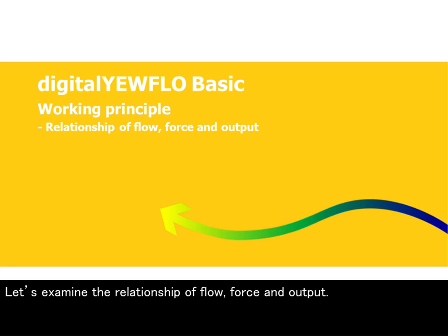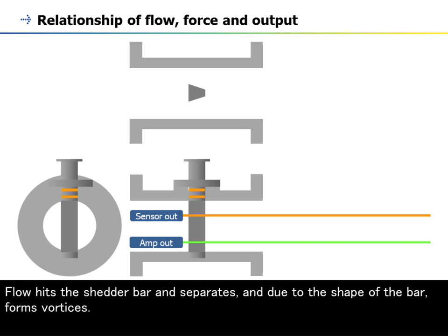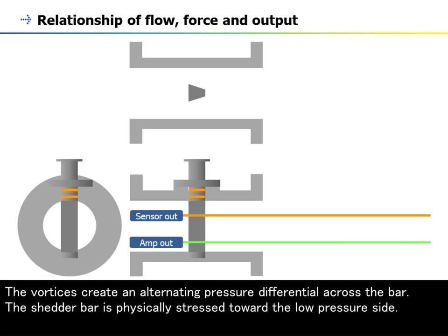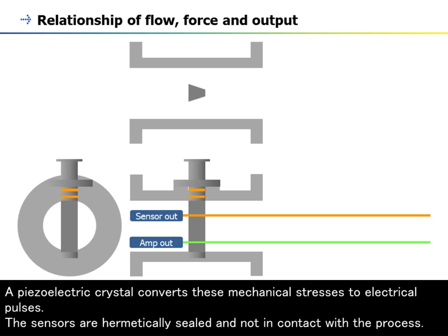Let's examine the relationship of flow, force and output. Flow hits the shedder bar and separates, and due to the shape of the bar, forms vortices. The vortices create an alternating pressure differential across the bar. The shedder bar is physically stressed toward the low-pressure side. A piezoelectric crystal converts these mechanical stresses to electrical pulses. The sensors are hermetically sealed and not in contact with the process.